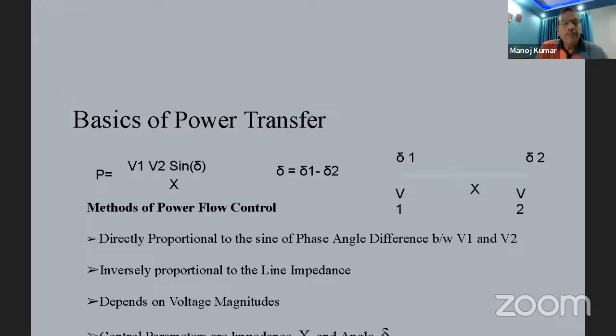Power transfer between the two points depends on the voltages at the sending and receiving ends, and the angle between them. These voltages are controlled by putting in shunt capacitors, STATCOMs, SVCs and many other devices. And if you want to transmit more power in the line, you put in series capacitors and reduce the line impedance. There is one more aspect, that is delta.